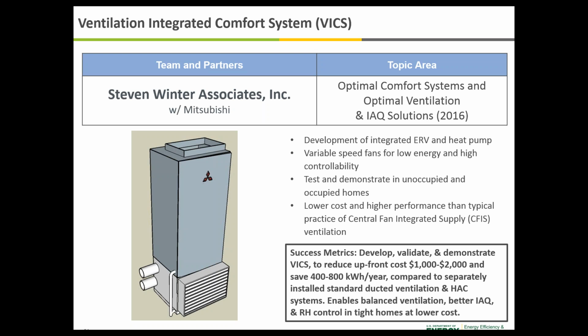Cost-wise, the two separately ducted systems have a higher installation cost. There's also the aspect of whether the correctly sized fan is running at each time with the CFIS system, which may rely on the central air handler fan rather than a more appropriately sized HRV or ERV fan. So what they're doing is combining those systems using variable speed fans, both in the ERV and in the air handler, so they can really dial in controllability and generate the ventilation, or the air conditioning and heating, that they need at a low energy level.